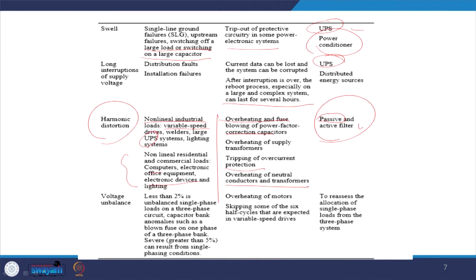So, blowing of the power factor correction capacitors, overheating of the supply transformer, we shall see in detail why it is so, tripping of the overcurrent protections, because the peak may increase because of the presence of harmonics, and overheating of the neutral conductor. This solution is provided by an active power filter or passive power filter. To keep the discussion short, because we require to complete our discussion in 20 hours, we shall put more emphasis now on the active power filter.